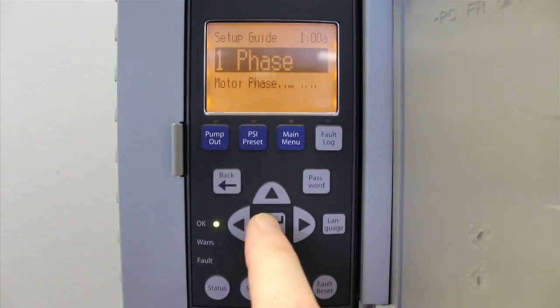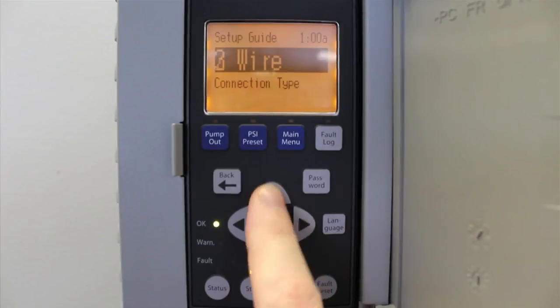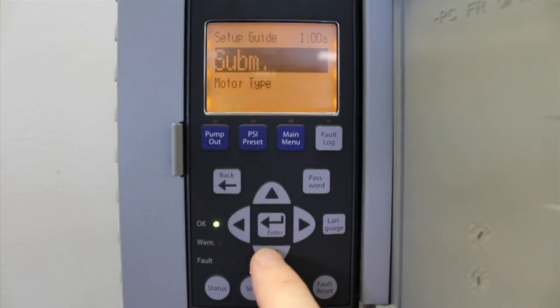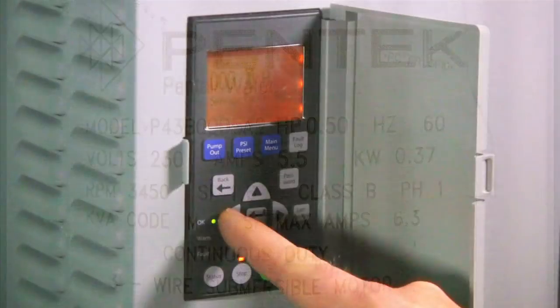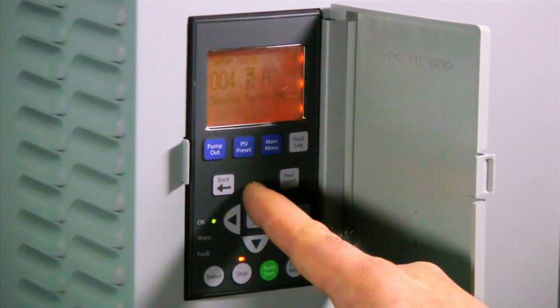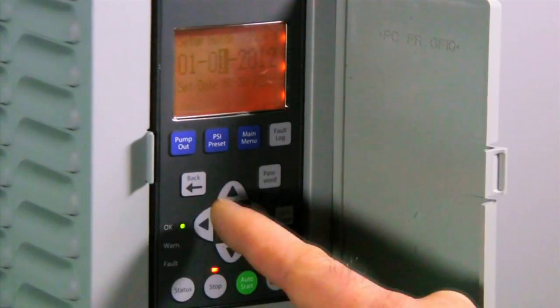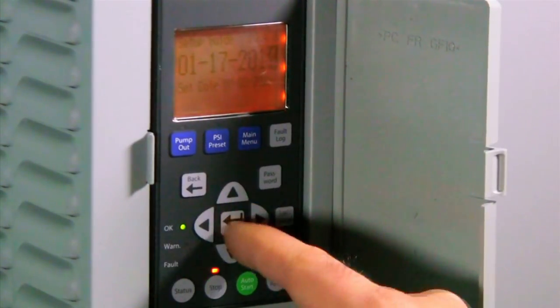Enter the motor phase, either 1 or 3, and then press Enter. For single phase motors, you'll select the connection type, either two or three wire. For three phase motors, you'll select the motor type, either submersible or above ground. From here you'll enter the service factor amps — this information can be found in the owner's manual or on a label on the motor. Once you've entered the proper information, press Enter. Set the time, then set the date, and the setup is complete.